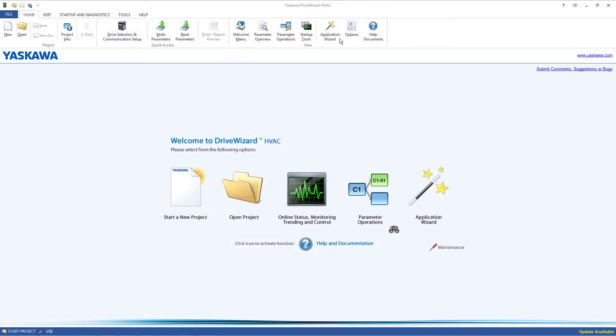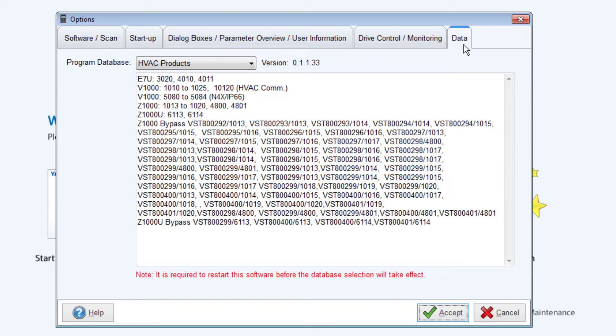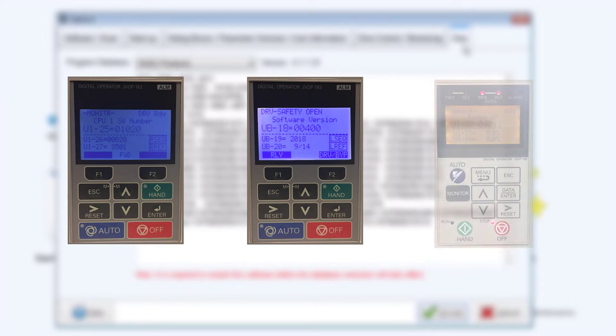You can find a list of all the supported firmware of the installed database by going into Options and selecting the Data tab. All of the numbers listed next to each drive series are the flash IDs. For 1000 series drives, the flash ID can be found in Monitor U1-25 for the standalone drive and UB18 for the bypass units. For E7 drives, check Monitor U1-14.